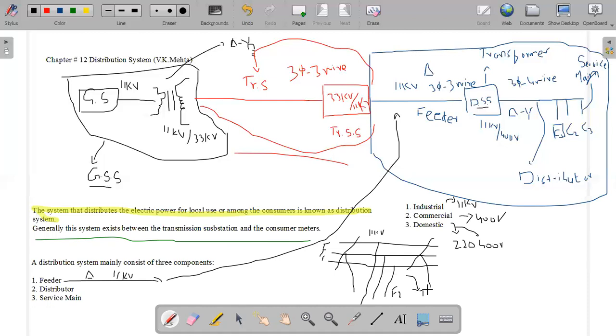In this taping, when you take a parallel connection, the current in these feeders gets divided, resulting in a lower value of current. But the main requirement of the feeder is that the current should remain the same. Therefore, we do not take any taping in the feeder.